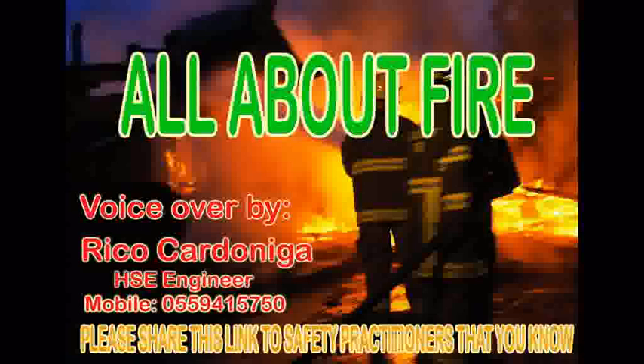Outline the main considerations when deciding on the siting of fire extinguishers. Accessibility, visibility, proximity to exits and escape routes, travel distances, support of the equipment off the ground, free from obstruction, protection from the weather, protection from other sources of damage.